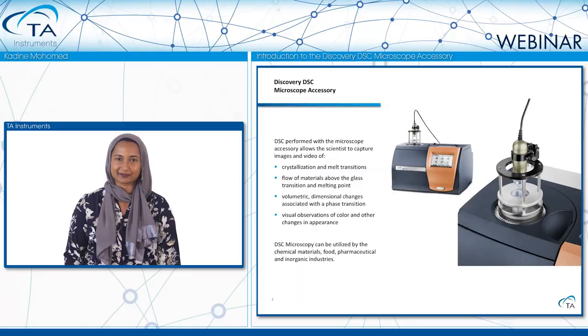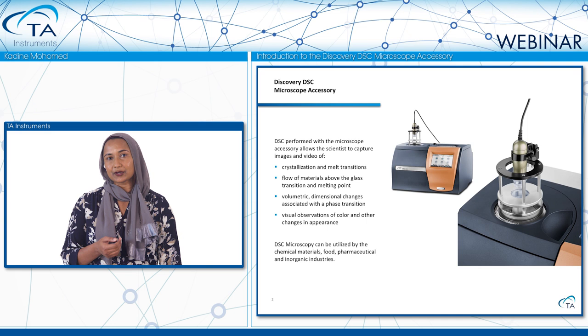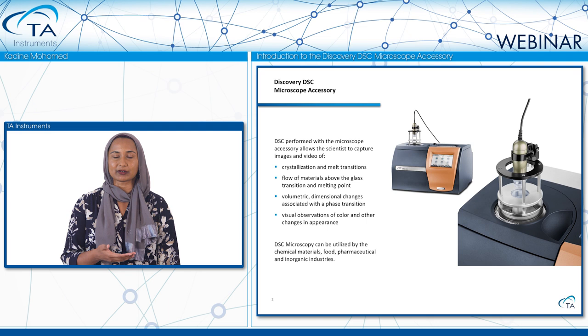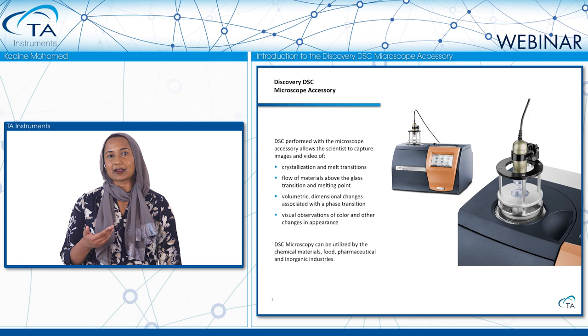With DSC thermograms, as you heat your sample, it may undergo an endothermic or exothermic step change or peak. And if you know the chemistry of your material, then it may be easy to interpret that as a glass transition, melt transition, crystallization peak, or cure reaction. But sometimes there are samples that undergo an endothermic peak where you may not know if that is a solid-solid phase transition or evaporation.